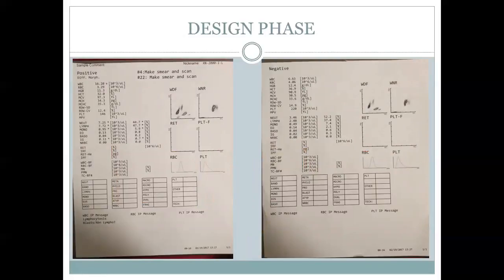Okay, so this is how the results look like. This is for the test. You can see on the right side the results are negative. All the counts are good, so it did not give us any flag. And on the left side you can see that it's showing positive, and it's asking us to make a smear and scan the slide, and you can see why it is positive and what it is positive for. So you can see lymphocytosis, or blasts, or abnormal lymphocytes. So it's telling us that the lymphocyte count is too high, and there could be a blast or abnormal lymphocyte present. So we have to review the slide to make sure all those things are right.